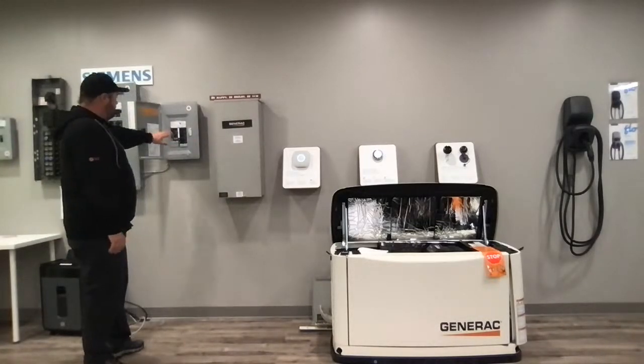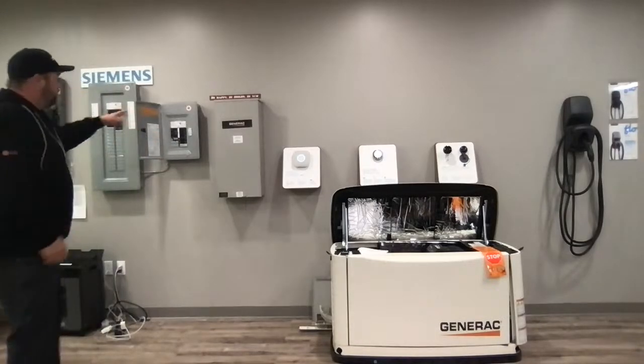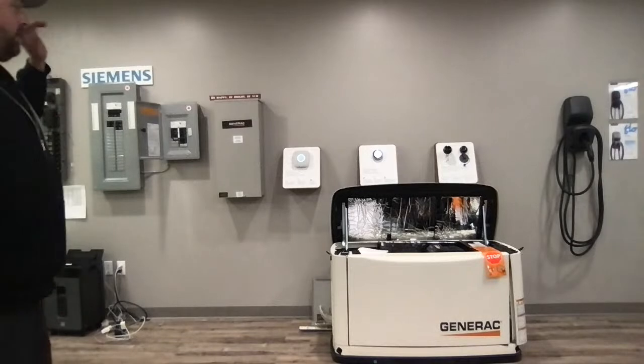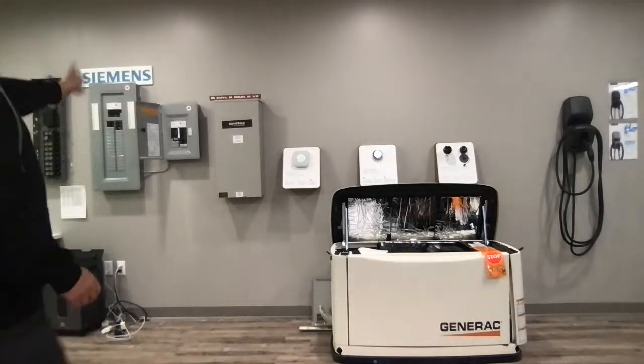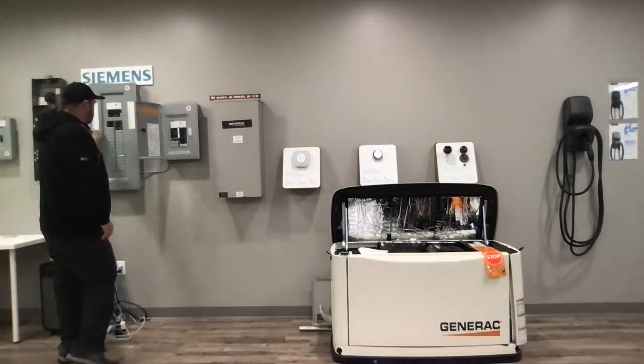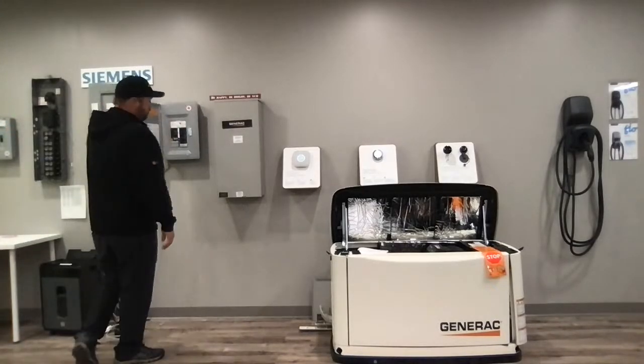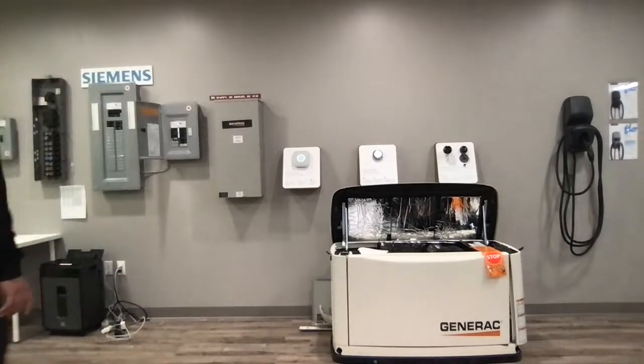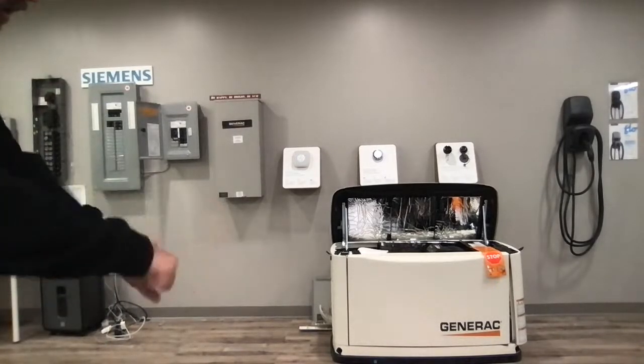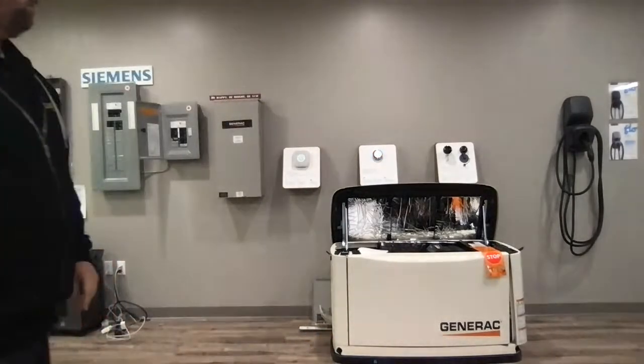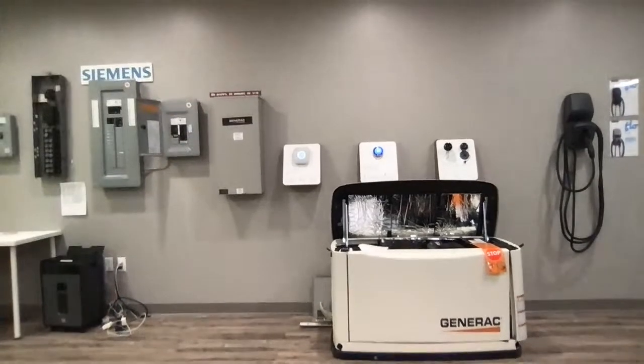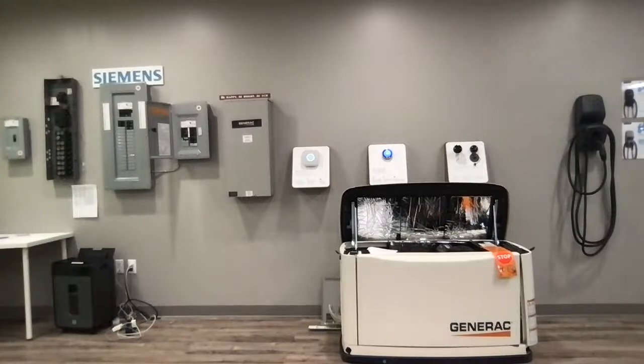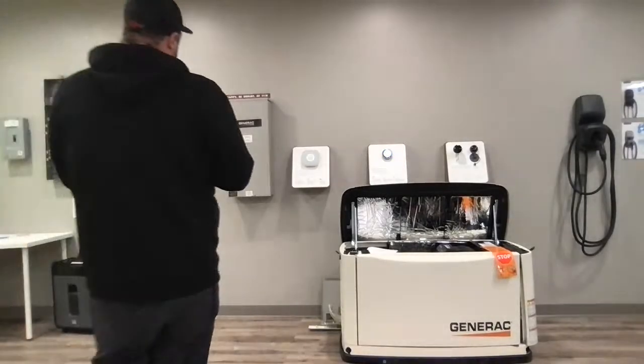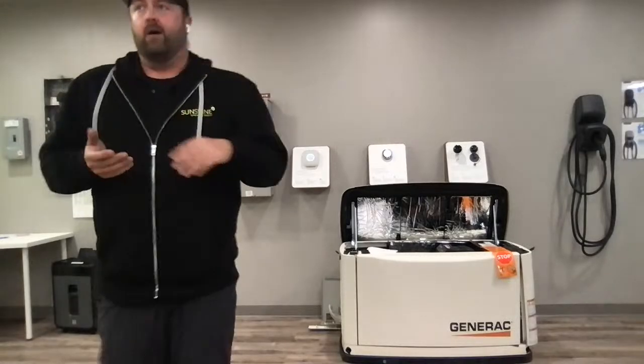The one that we do a lot of is this - just a straight up generator panel. Essentially what we do is isolate your electric panel from the grid, so that if the power goes out you can put power to that panel without sending power through to the grid. It all has to be done through Nova Scotia Power, we have to get a permit and everything like that, but you can do a lot of stuff with it. It's basically a plug on the outside of your house - you plug it into your generator, fire the generator, and it powers everything we put into that panel. It could be a small heat pump, fridge, deep freeze, internet, kitchen plug, bathroom lights - kind of like your essential stuff.